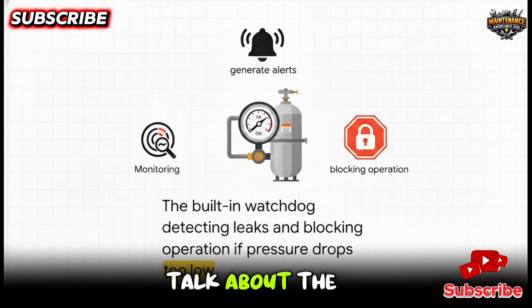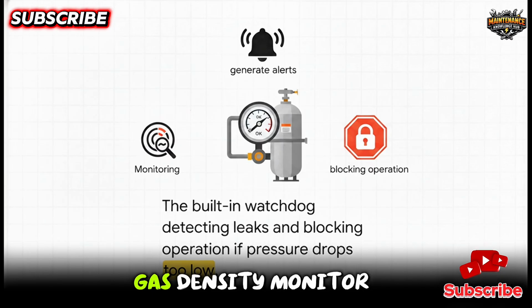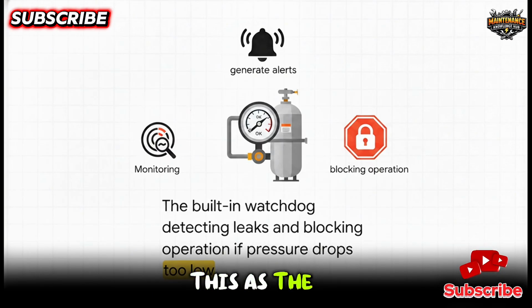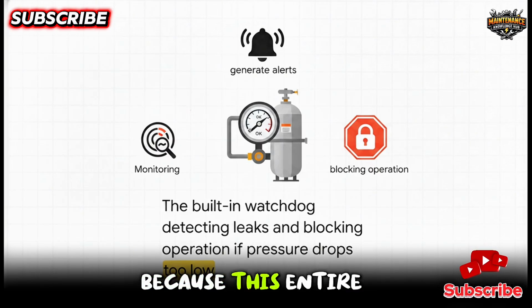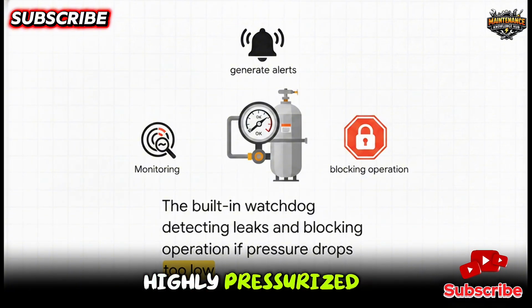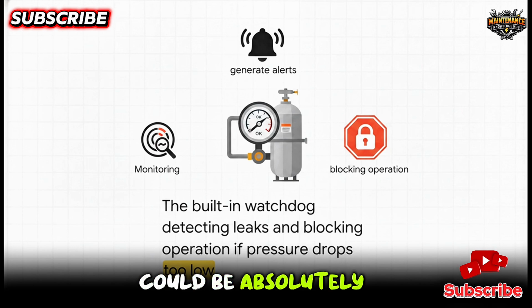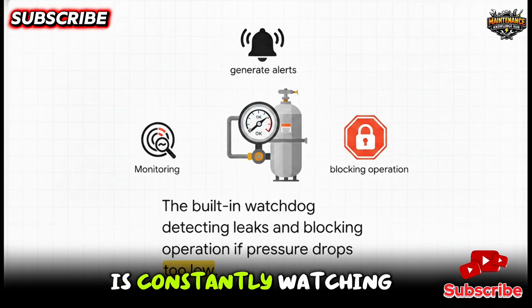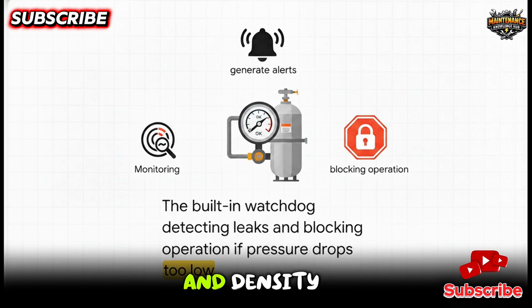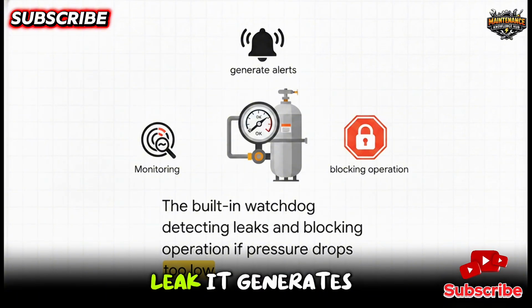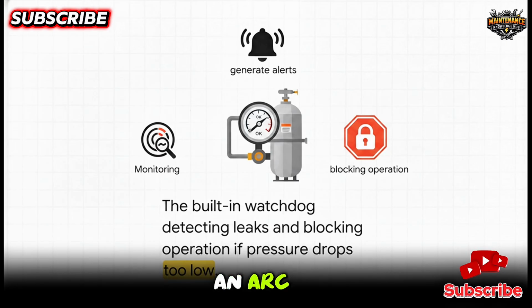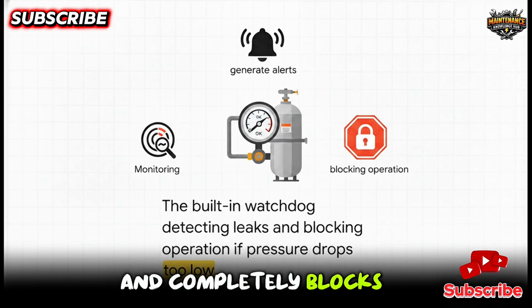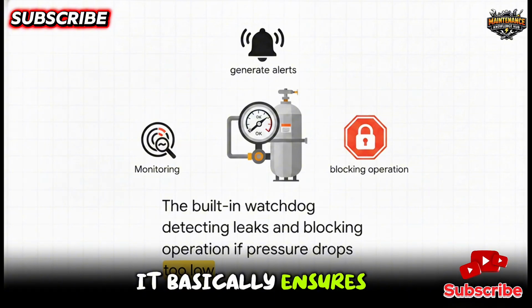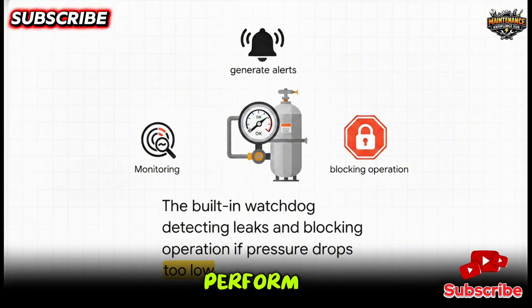We really can't talk about the internal components without highlighting the gas density monitor. You can kind of think of this as the breaker's built-in watchdog, because this entire system completely relies on highly pressurized SF₆ gas to stop an electrical arc. Well, a leak could be absolutely catastrophic. So this monitor is constantly watching the SF₆ gas pressure and density. If it detects even a small leak, it generates alarms. And if the pressure drops way too low to safely extinguish an arc, it actually steps in and completely blocks the breaker from operating. It basically ensures the gas chamber is always ready to perform.